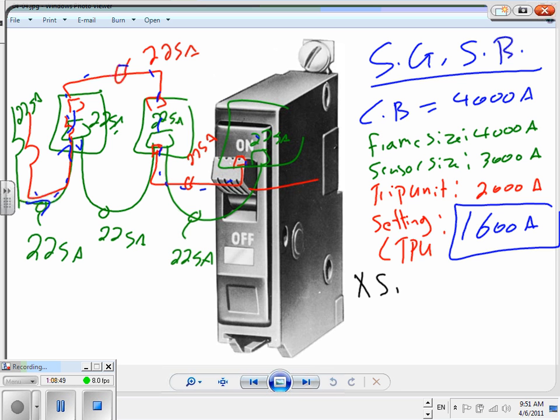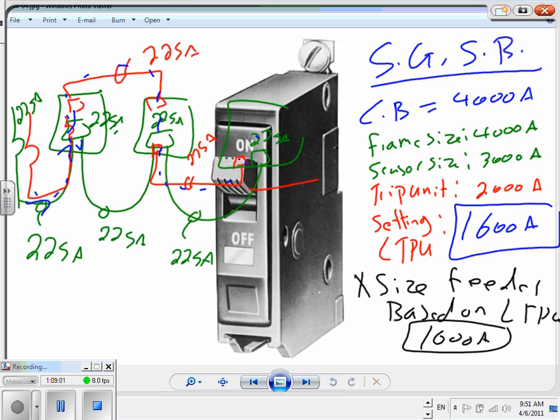So this is very important: size the feeder based on long time pickup, which is 1,600 amp. So Brad, for all practical reasons, that circuit breaker you're looking at, in reality, acts like a circuit breaker with 1,600 amp. When I size the cables, I size based on 1,600 amps.